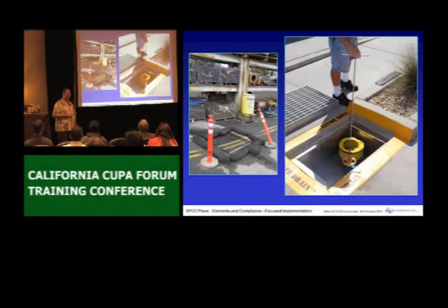They have 30 drains around their facility located on a peninsula in the port, right? Something hits the storm drain, in about 10 seconds it's out in the harbor. They have a lot of fuels out there, right? They installed safe drains everywhere. Fabulous. Doesn't matter where they move their stuff, their general containment, safe drains, all passing. Fabulous. Maybe not this, the saturated barriers.